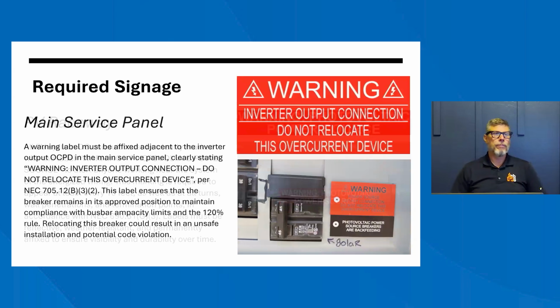For the interior of the panel, this is the one that you're going to see. This is the close-up of the one we had just saw. It says, warning, inverter output connection, do not relocate this overcurrent device. This must be in there and it must be permanently affixed. If you do not see it, that is a safety concern, that is a call out. That is also going to be how we determine the 120% rule. We have to know that that is truly for the solar.